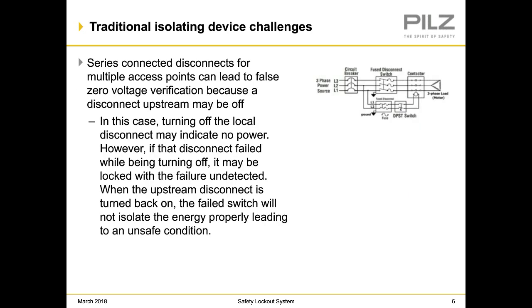Series connected disconnects for multiple access points can lead to false zero voltage verification because a disconnect upstream may be off. So in this case, turning off a local disconnect may indicate no power. However, if that disconnect failed while being turned off, it could still be locked and the failure is undetected. When the upstream disconnect is turned back on, the failed switch will not isolate the energy properly, and this could lead to an unsafe condition.